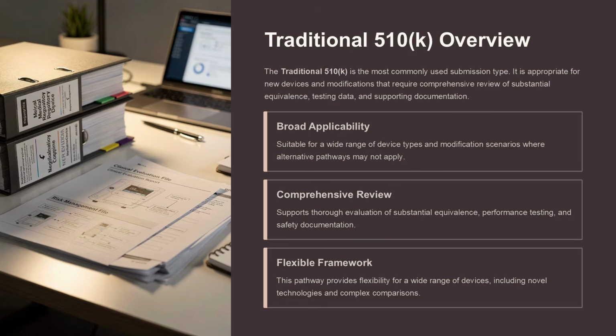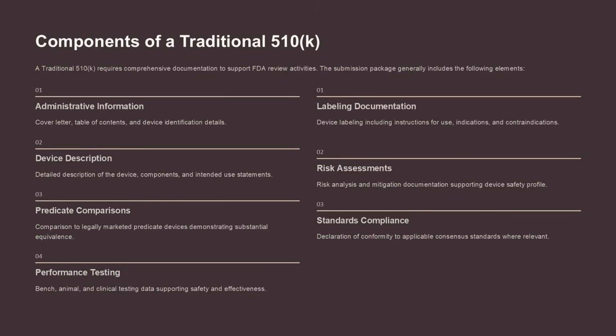It is appropriate for new devices and modifications that require comprehensive review of substantial equivalence, testing data, and supporting documentation. This pathway provides flexibility for a wide range of devices, including novel technologies and complex comparisons. A traditional 510(k) requires comprehensive documentation to support FDA review activities.